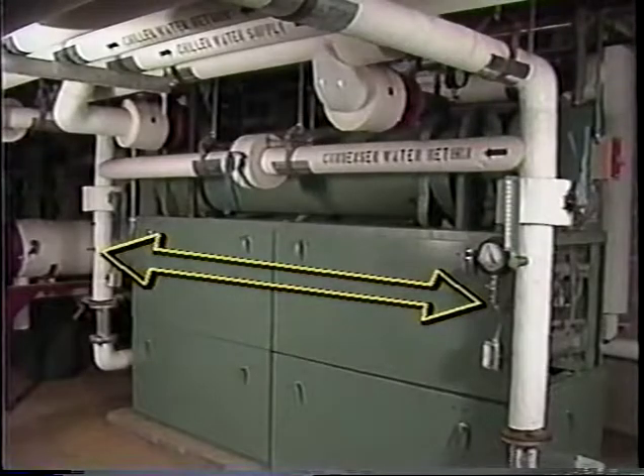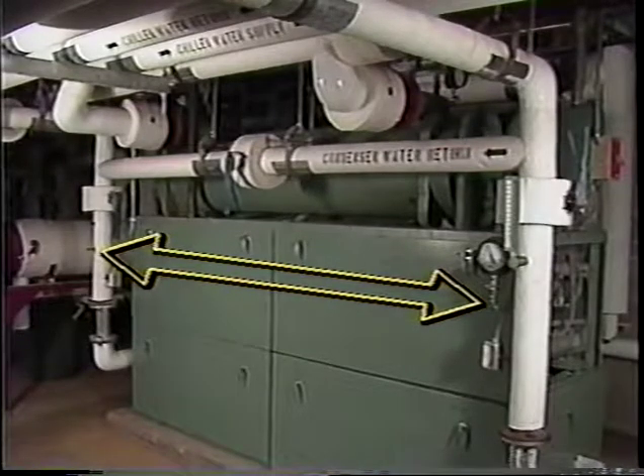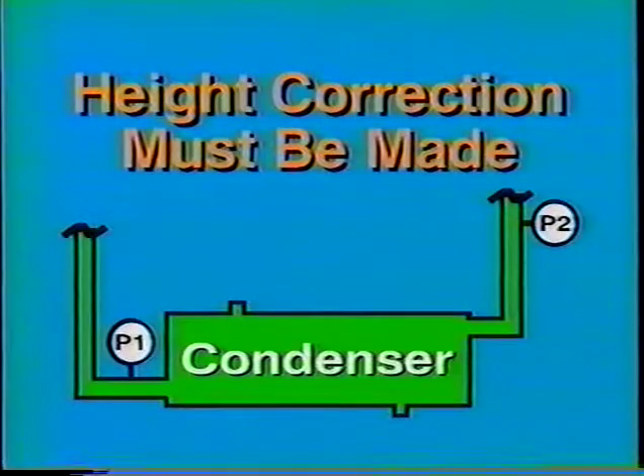Pressure taps for taking pressure readings across the condenser should be as close to the inlet and outlet as possible and at the same height. If there is any difference in the height of the gauges, a correction will have to be made. We'll discuss this in more detail later in the program.